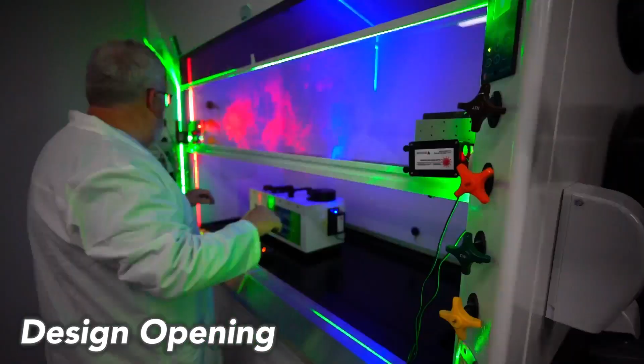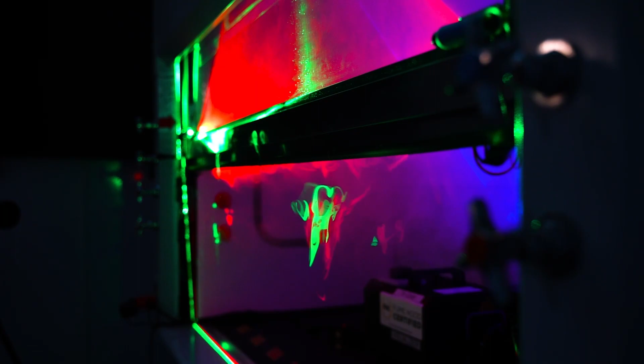The design opening is the working height that the system was designed for. It's often around 18 inches, and many hoods have sash stops at the design position. So lower the sash to the design opening, take a few steps back, and just observe and watch to see if you can find any loss of containment light up in green. Here's an example of something like a cross draft affecting a hood at its design opening. Cross drafts could come from many different things. You definitely don't want to see this much green smoke coming out.